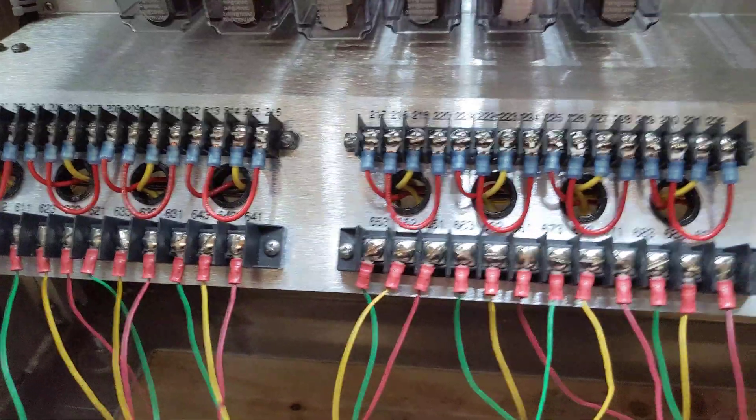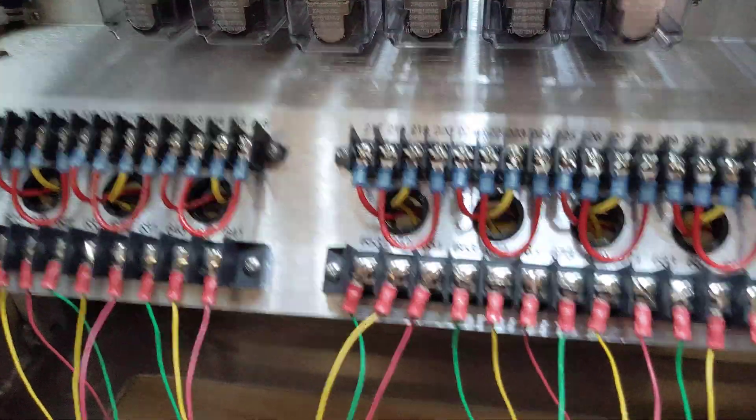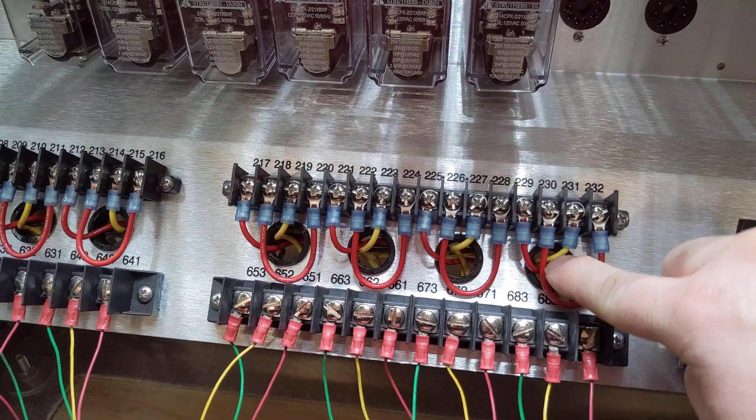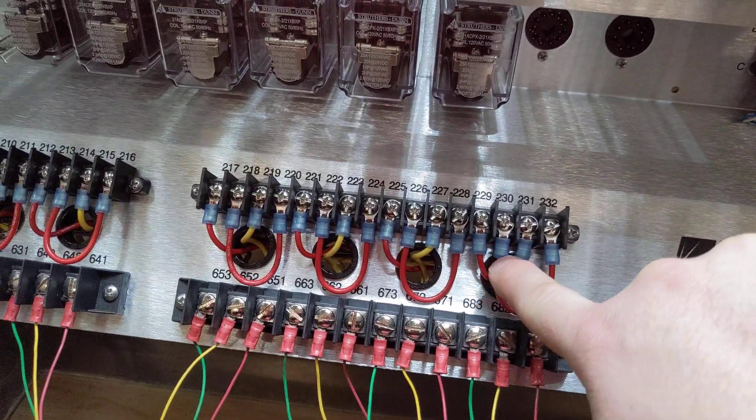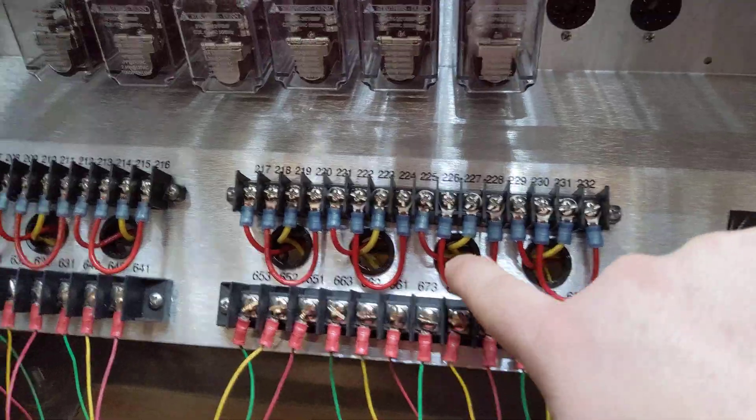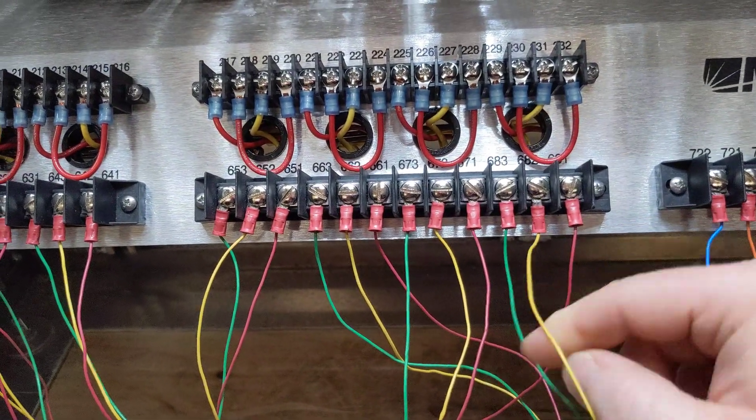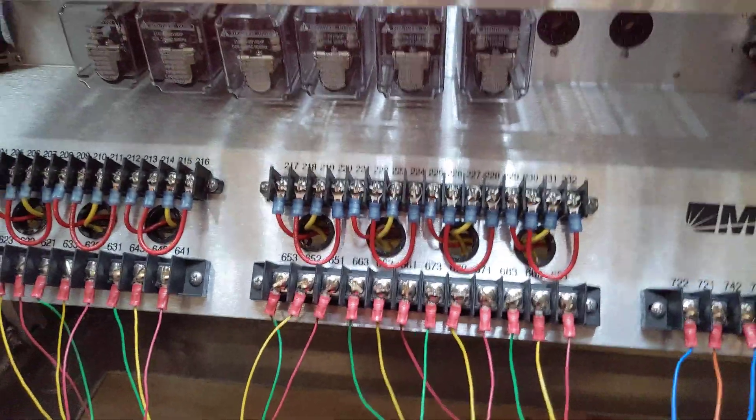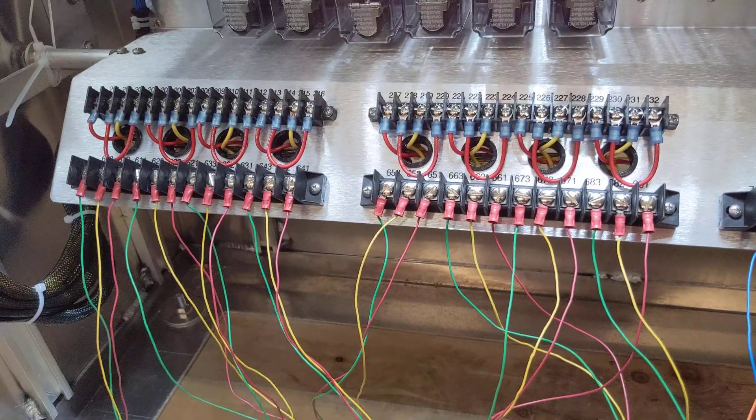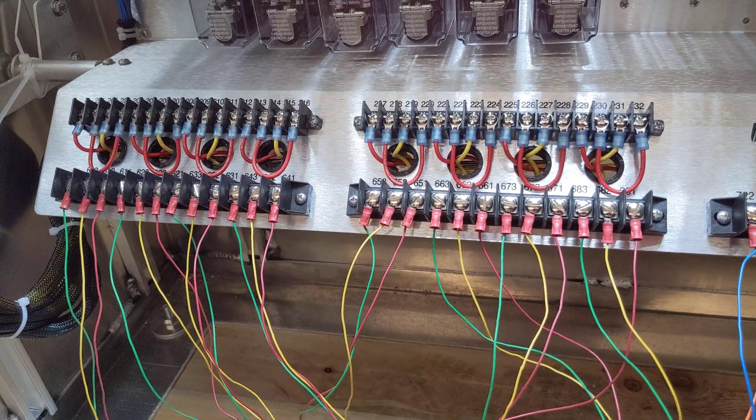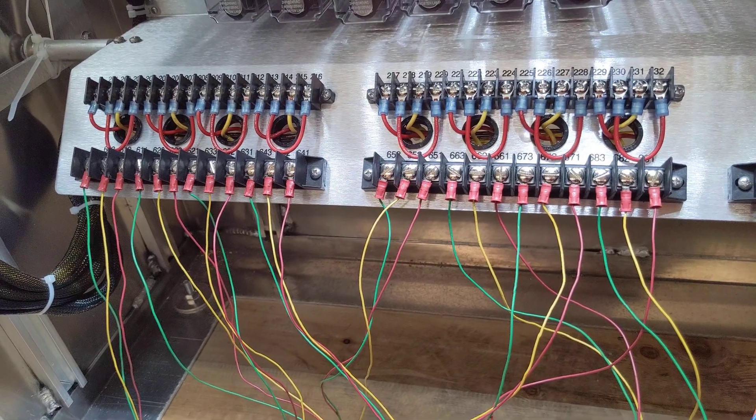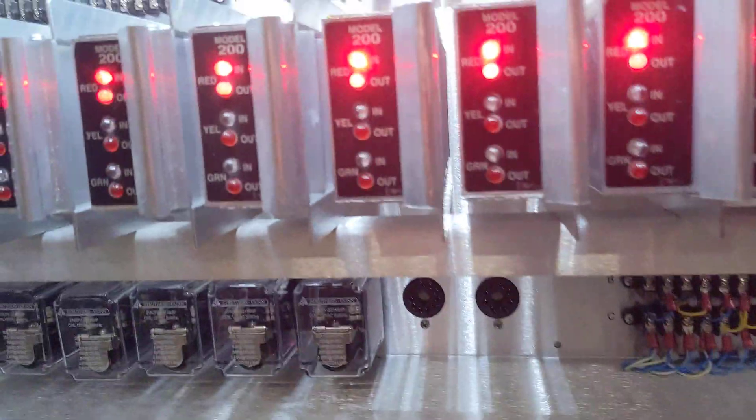And this guy is wired to these flash program terminals, which in turn passes the output onto the reds here, because this cabinet is configured to flash all reds. Now, if I were to change the input here for the yellow to be here where the red is on this cabinet, then the yellows would flash and not the reds. That's all that is, basically, is mapping. So some places will allow for one direction to flash yellow while the other direction flashes red.